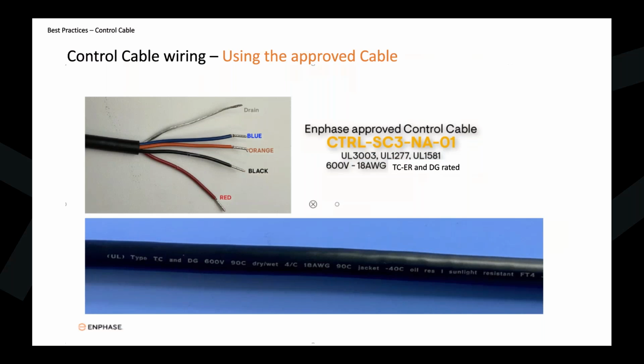I was on a site just last week where they didn't have it. When we got to commissioning, we couldn't get any communication within the batteries. So we had to power everything down, undo everything, and wire it up with this control cabling. As soon as we did that and fired everything up, it worked. So I want to make sure everyone understands this is the only approved control cabling for communications allowed within our system.